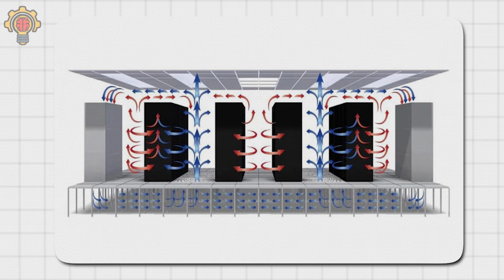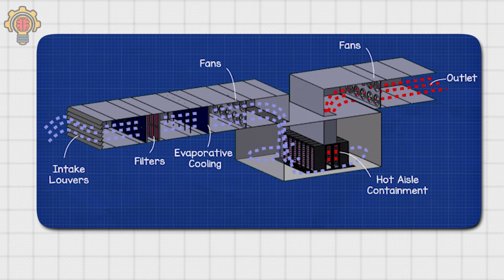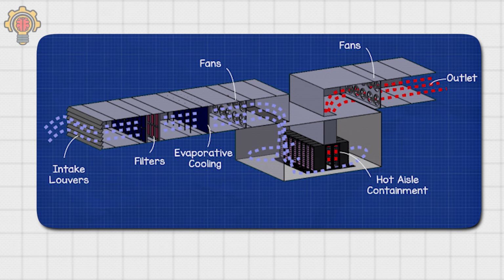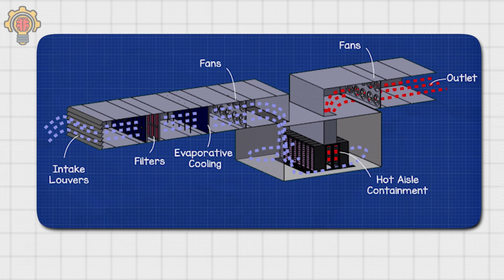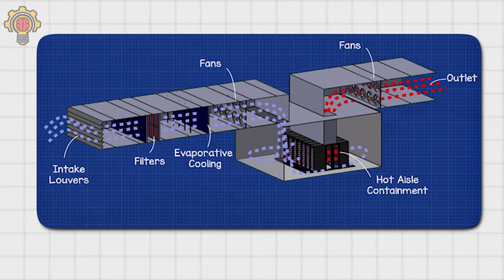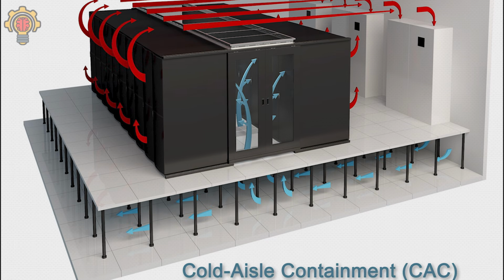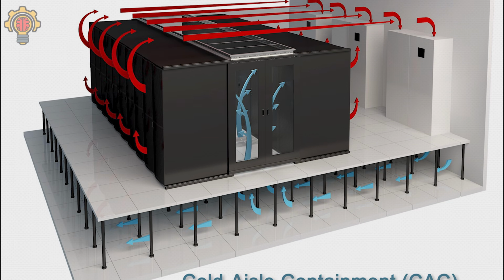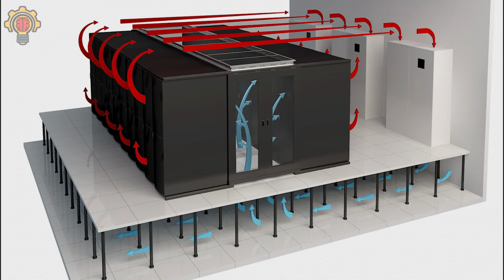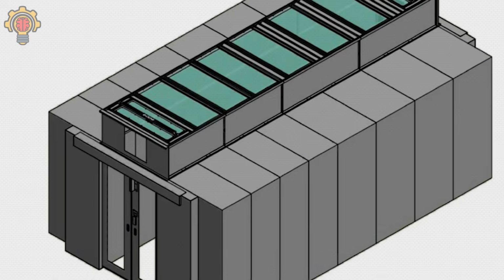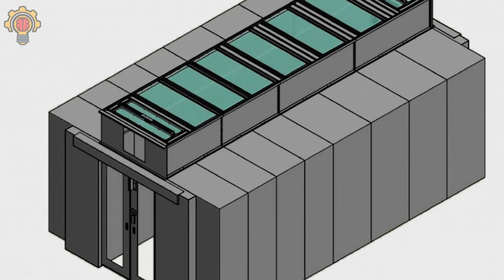So engineers developed something called containment systems. Instead of allowing hot and cold air to move freely throughout the room, physical barriers were added to separate them completely. In a cold aisle containment system, also called CAC, the cold aisle is enclosed using doors and ceiling panels. Cold air is trapped exactly where servers need it most.